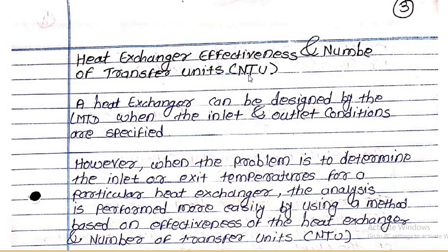But in some problems we do not know the inlet temperatures or the outlet temperatures, any of the inlet or outlet temperatures, or any mixed combination. In that case it is very difficult to design the heat exchanger by using the LMTD method. So in that case we should apply the heat exchanger effectiveness and number of transfer units method.